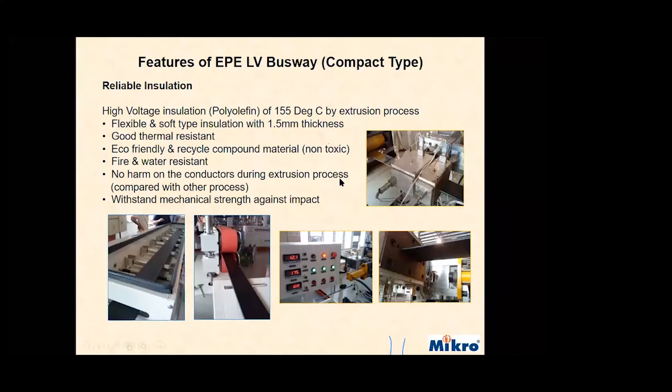This is our insulation — called polyolefin, rated at 155 degrees Celsius. The insulation process is an extrusion process. Polyolefin is a flexible and soft type insulation with 1.5 mm thickness. It has good thermal resistance, is eco-friendly, non-toxic, and provides good fire and water resistance. The extrusion process means no harm on the conductors, and polyolefin can withstand mechanical strength against impact.